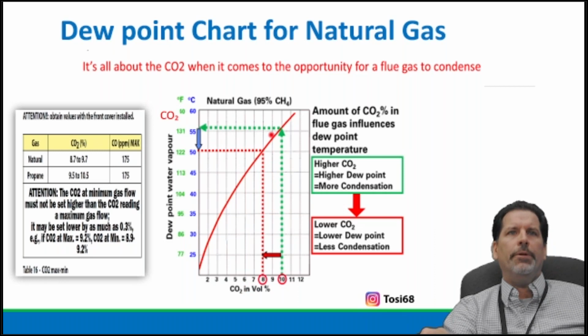If we go up with return water now, right, back from the system, our 20-degree split, even if we went out at, let's say, 150, because it's a system that needs a little bit of a higher water temperature on maybe a 10-degree night, not a 15 now, right? So we go out at 150, we come back at 130. You'll see that's where our dew point is. We start condensing sooner, even at that 130 return.